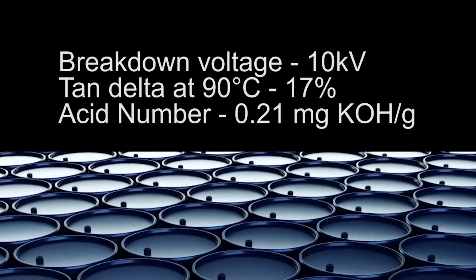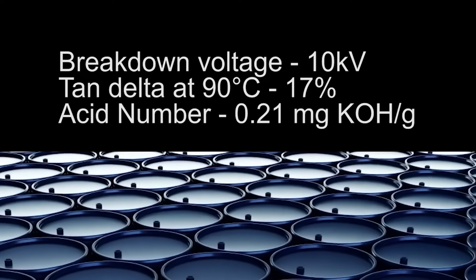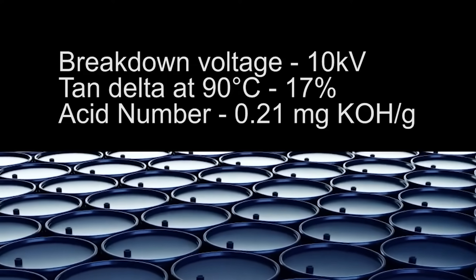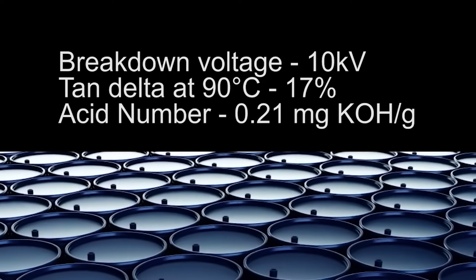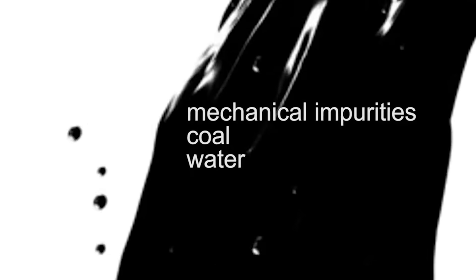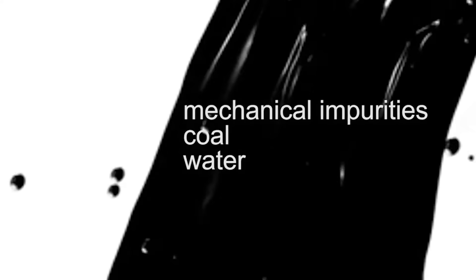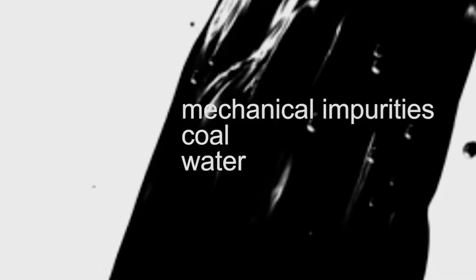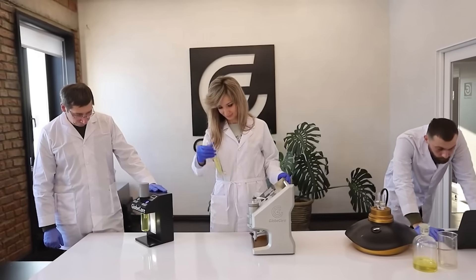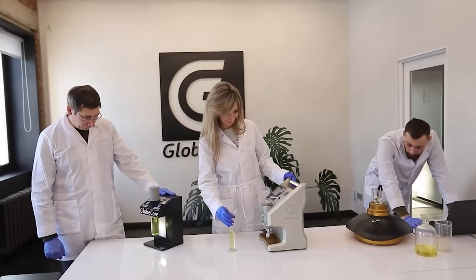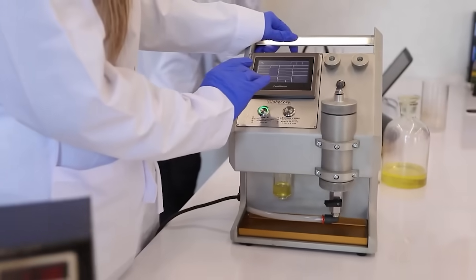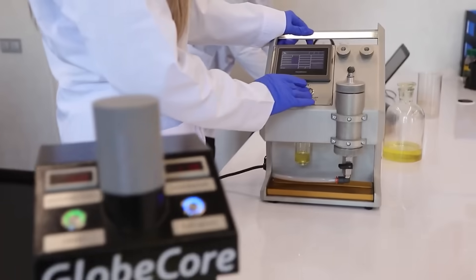Breakdown voltage: 10 kV. Dielectric loss tangent at 90 degrees Celsius: 17%. Acidity index: 0.21 mg KOH per gram. Furthermore, the samples taken contain mechanical impurities, carbon deposits, and water.